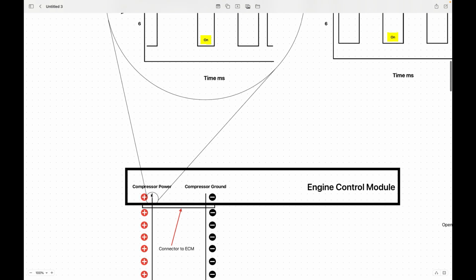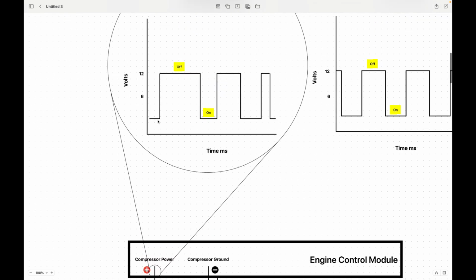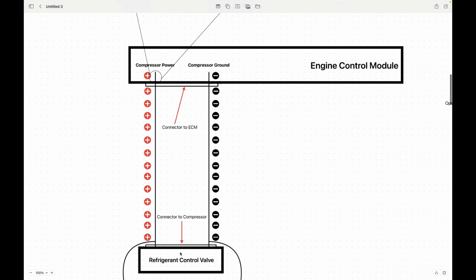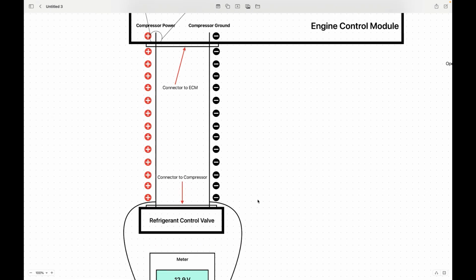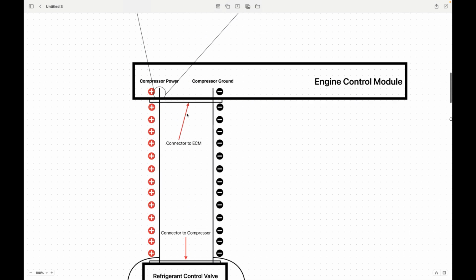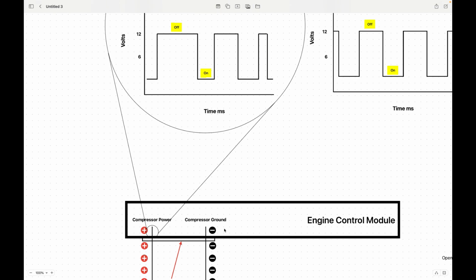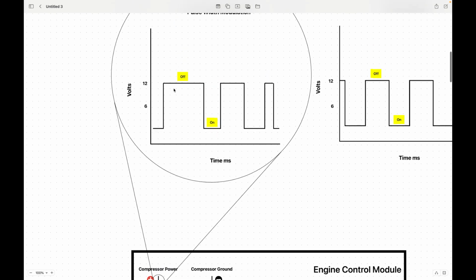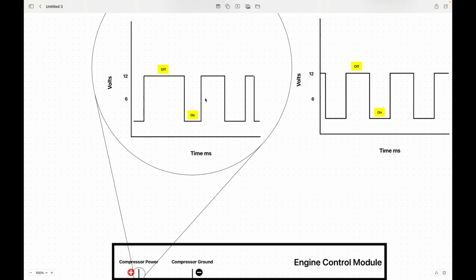Measured at this point, it should be 0 volts when the valve is turned on. And then as soon as the valve turns off, it would be as if you're opening this circuit. So no current is flowing, it's an open circuit, and now you can see full potential voltage from the ECM in this circuit, and then it goes up to whatever the ECM available voltage or charging system voltage is that the ECM is using to supply this.